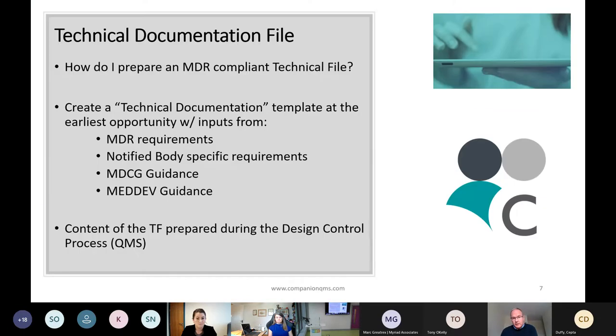So how do I prepare an MDR compliant technical file? There is a significant amount of detail to achieving this, but you can help yourself by preparing a technical documentation template at the earliest opportunity. There's so much to take on board that it's necessary to determine what the goalposts are by mapping that out in a template. You can do that by reviewing the MDR requirements themselves, seeking out wherever the legislation mentions technical documentation, and determining whether that's something you need in your template and your end requirements.